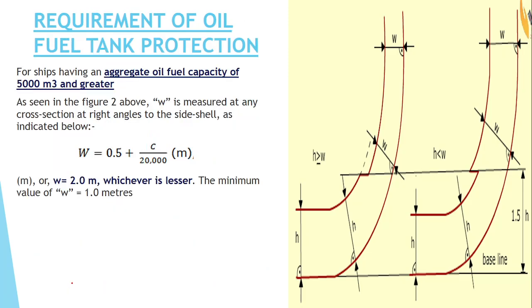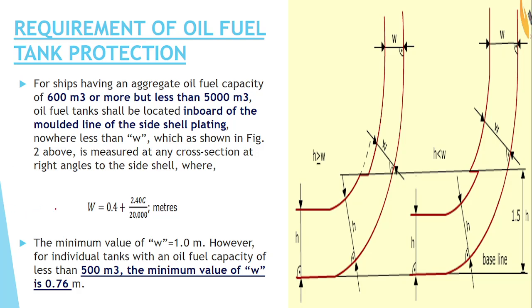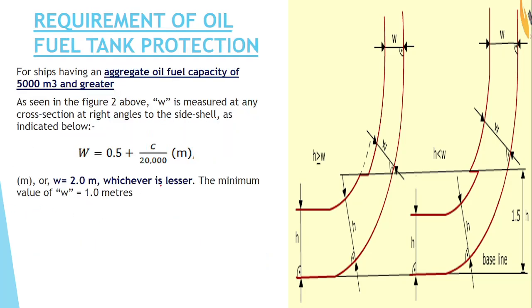If your aggregate fuel oil capacity is more than 5000m³, you have to follow a new formula. The difference is that the first formula uses 0.4 + 2.4C/20,000, whereas the new formula uses 0.5 with no 2.4C term. Whatever value comes from this formula, or 2 metres, whichever is the lesser, you have to take. So there are three cases regarding the width.